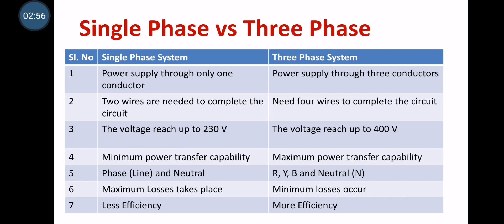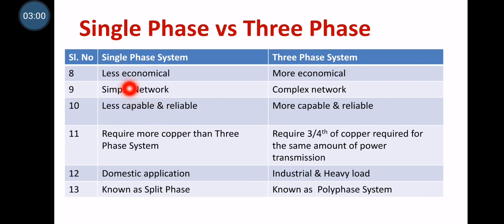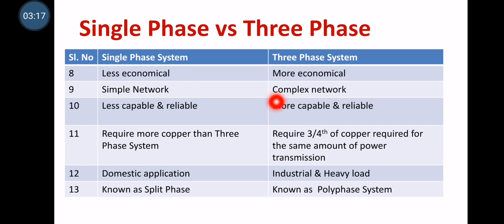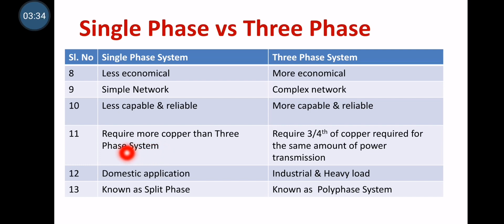These are a few differences. Single-phase system is less economical for high power transmission, whereas three-phase system is highly economical for high power transmission — that is why three-phase system is implemented for high power transmission. Single-phase system is too simple, but three-phase system is more complex. Single-phase system is less capable and reliable, but three-phase system is more capable and reliable. For the same amount of power transfer, single-phase requires more copper, whereas three-phase system requires only three-fourths of the copper — saving copper and making it economically favorable.